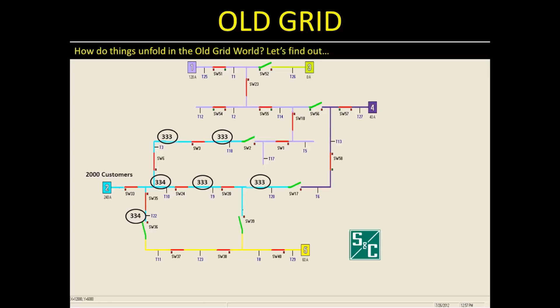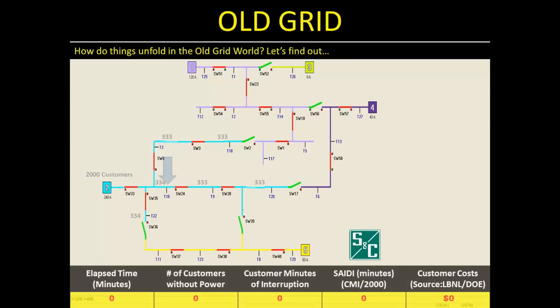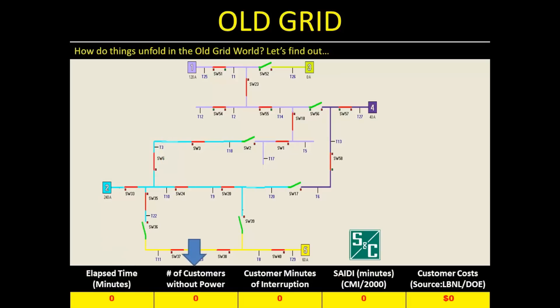This feeder is going to have a short circuit, and we will see how the old grid deals with it. We'll keep track of elapsed time in minutes, the number of customers without power at any point in time, and the cumulative minutes customers have been out of service. We will also track an index called SAIDI — the System Average Interruption Duration Index — which tracks the number of minutes the average customer is out of power. SAIDI equals cumulative minutes of interruption divided by the number of customers, which on our feeder is 2,000.